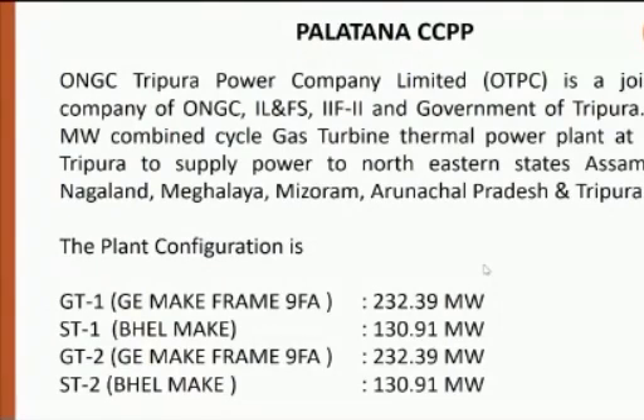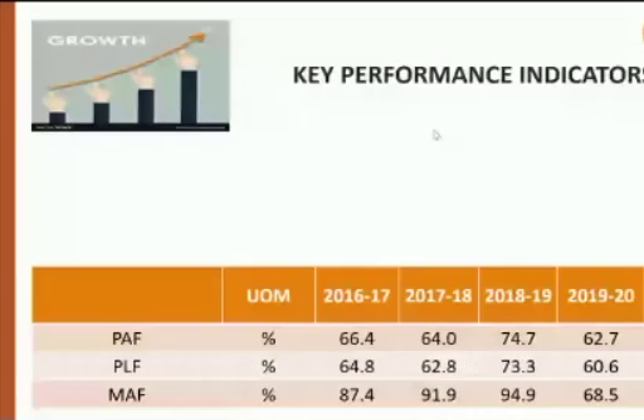The plant is configured in such a manner that it can run only in the combined cycle. It can't run in the open cycle mode. This is done for better energy utilization to get a better heat rate. These are the key performance indicators of past years, including this year also. You can see the plant availability factor and machine availability factor is quite good. We are getting sufficient gas from ONGC, and we could operate the machines in an optimum manner with best O&M practices. I will share a few of the O&M practices in the subsequent slides.